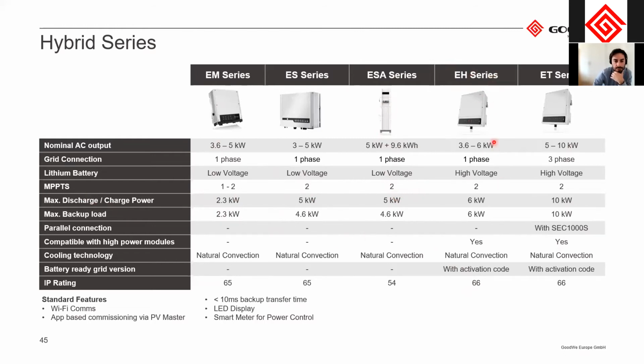The EH inverter is the only single-phase inverter compatible with high voltage batteries. So for example, the BYD batteries. It is one of our newer single-phase hybrid inverters and has 2 MPPTs and ranges between, similar to the rest, 3.6 kilowatt up to 6 kilowatt. The ET here is a 3-phase inverter from 5 up to 10 kilowatt. Also, of course, compatible with high voltage batteries since it's a 3-phase inverter.